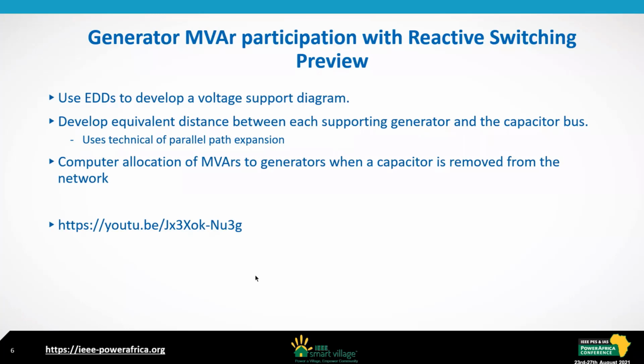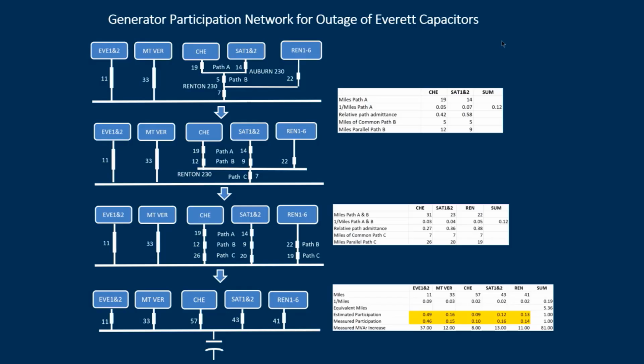And that's the foundation to really quickly see which generators will provide the most megavar support to an event on that bus. The support basically comes from the generators that have the shortest electrical distance to the bus where the capacitor or reactor will be switched. In this exercise, our goal is to develop a network that shows how the different generators will participate if there is an outage of the Everett capacitors.